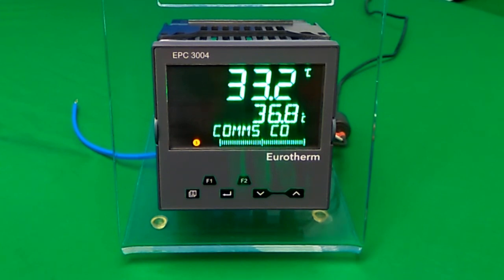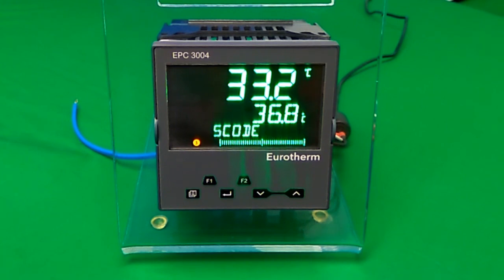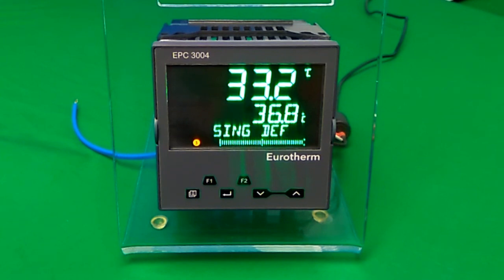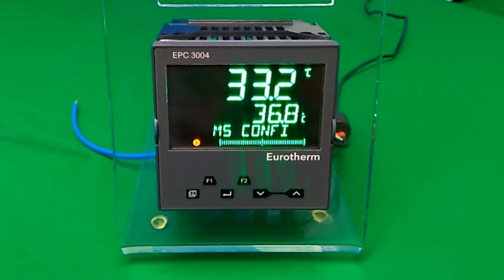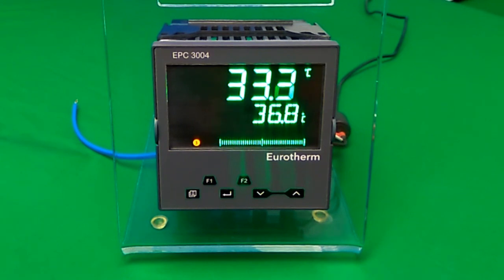This demo will show you how to configure and then run a program via the front panel of the EPC3000. For example, a program to ramp a temperature setpoint over a specific profile. The demo assumes that QuickCode 1K3XX configuration is already running in the EPC3000, therefore the wiring between the PID and program function blocks already exists.